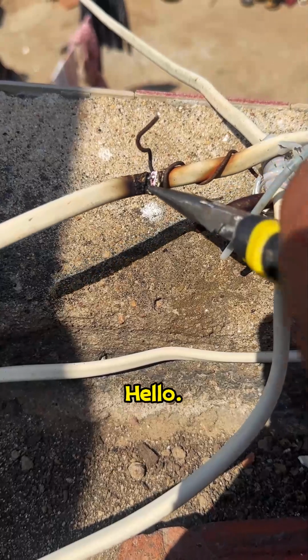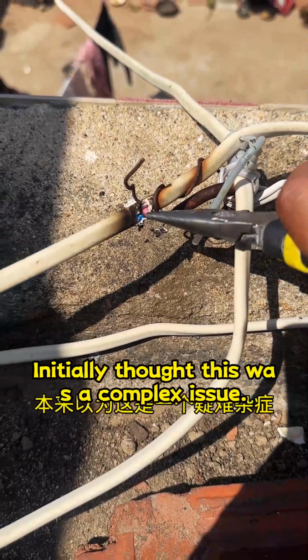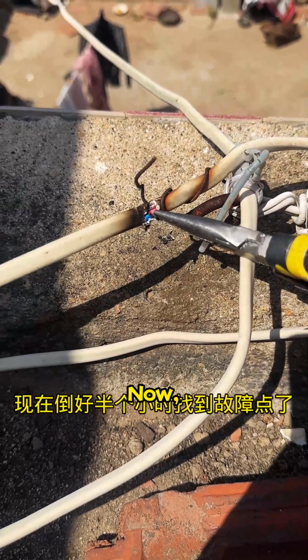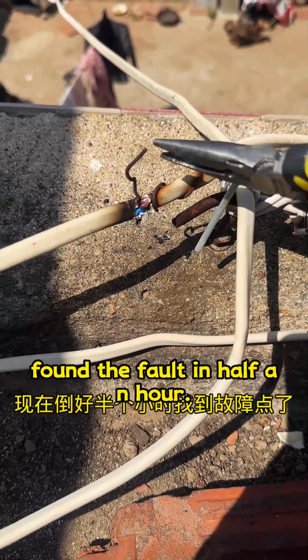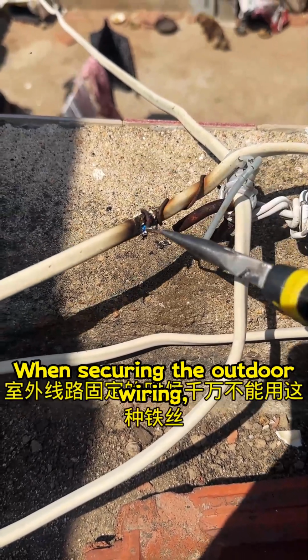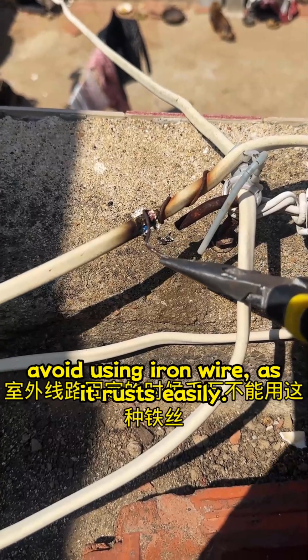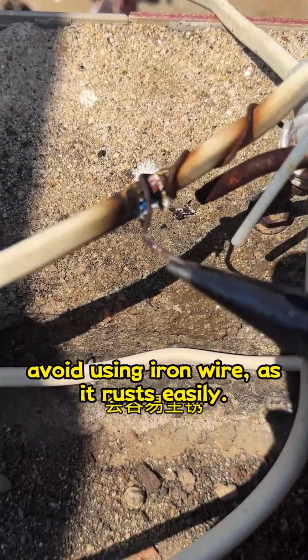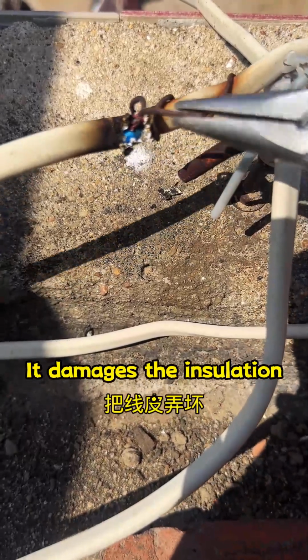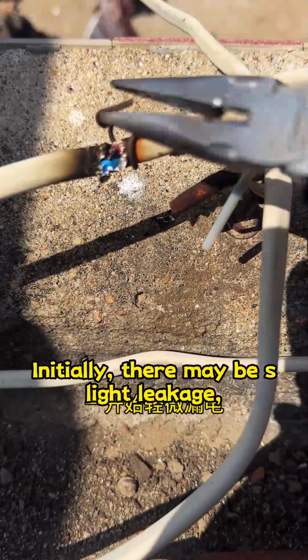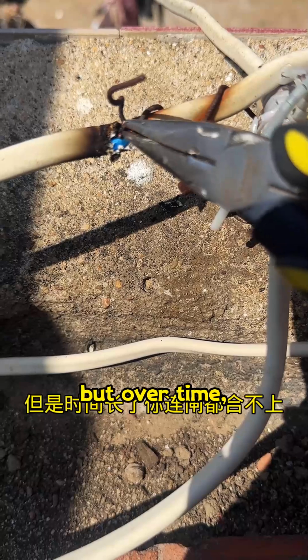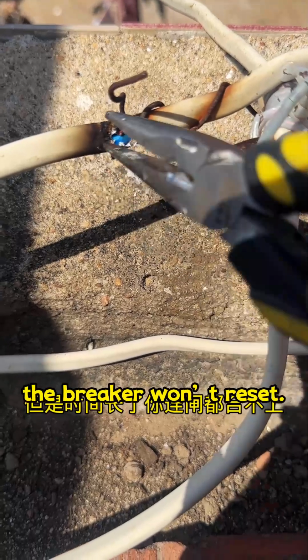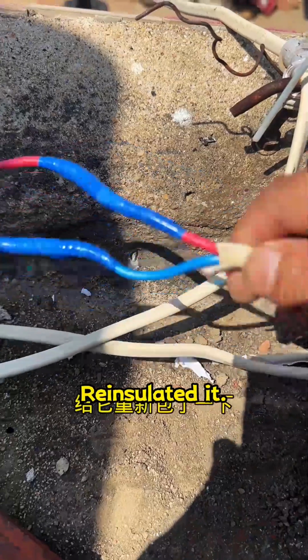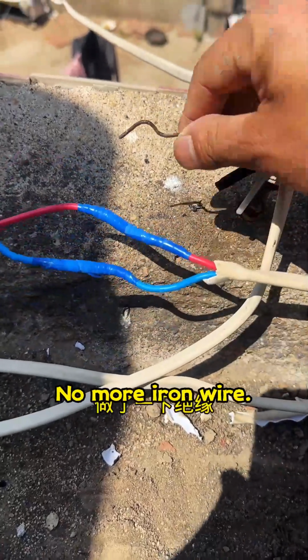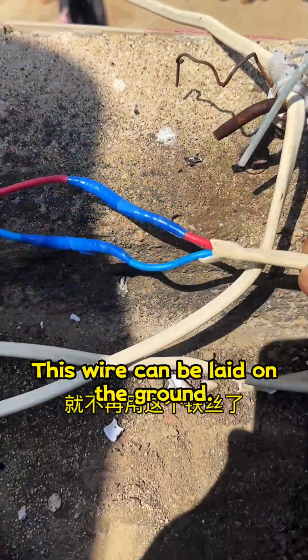Initially thought this was a complex issue. Now, found the fault in half an hour. When securing the outdoor wiring, avoid using iron wire as it rusts easily. It damages the insulation. Initially, there may be slight leakage, but over time, the breaker won't reset. Re-insulated it. No more iron wire. This wire can be laid on the ground.